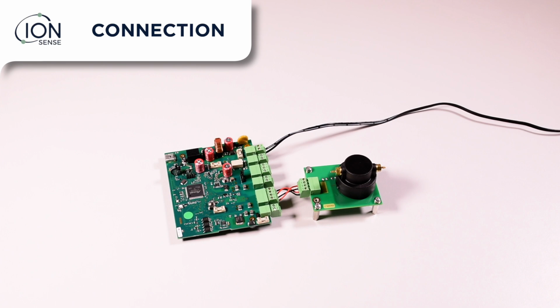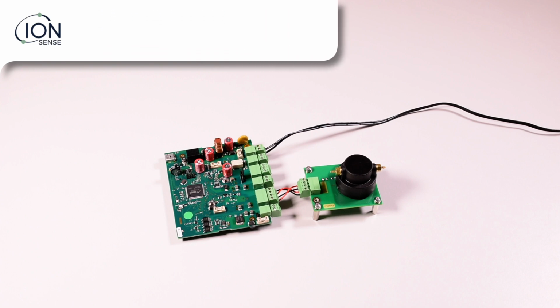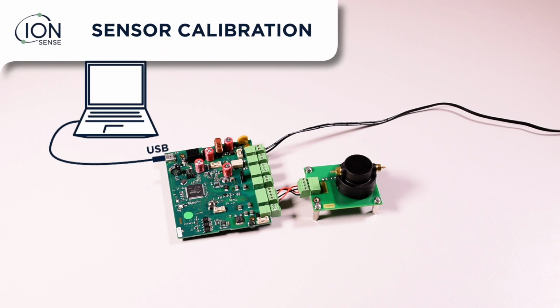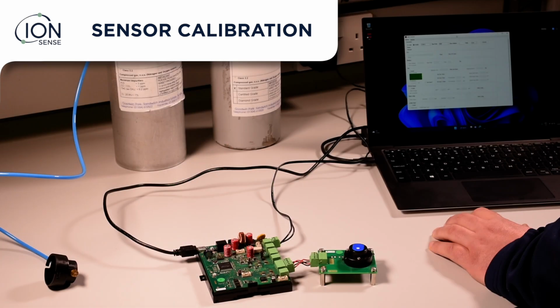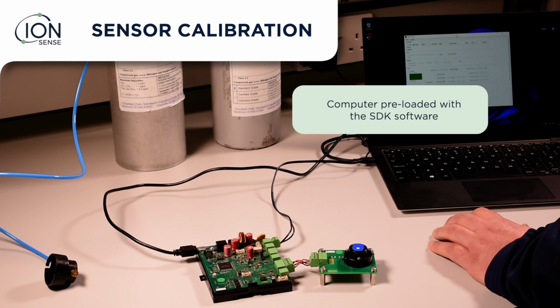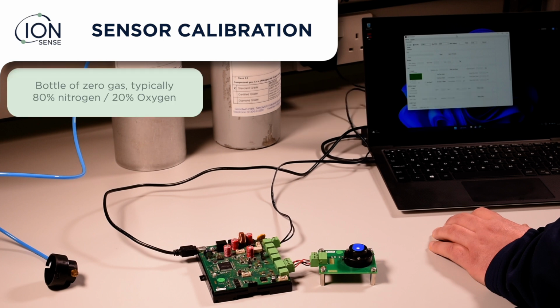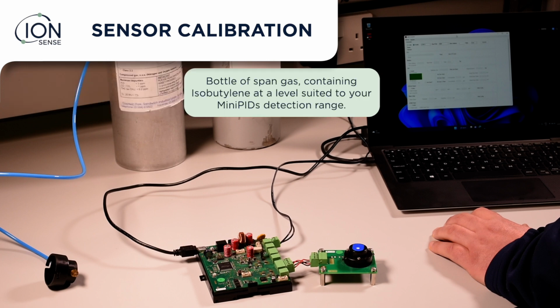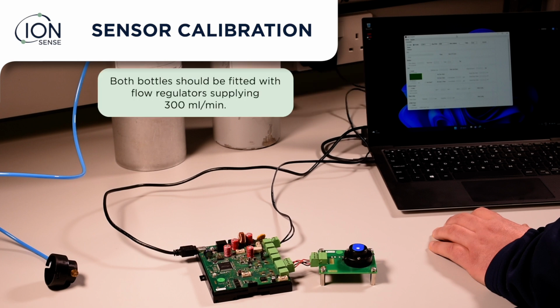This next section shows how to set up and calibrate the MiniPID sensor via the USB cable. The USB cable connects here. For this procedure, the following equipment is required. A computer preloaded with the SDK software. A bottle of zero gas, typically a nitrogen-oxygen mix. And a bottle of SPAN gas, containing isobutylene at a level suited to your MiniPID's detection range. Both gas bottles should be fitted with flow regulators supplying 300 ml of gas per minute.